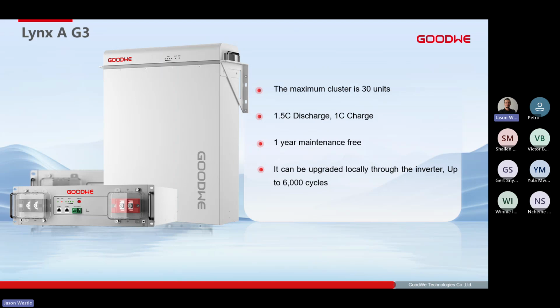All of our batteries at GoodWe can be upgraded locally through the inverter, and they can also be upgraded remotely. How often we do firmware upgrades or need to upgrade on the BMS side is very, very slim. The batteries that GoodWe manufacture are manufactured and programmed or protocol only for GoodWe inverters. So the chances of massive firmware updates or massive firmware changes needing to be done on the inverters are slim to none.